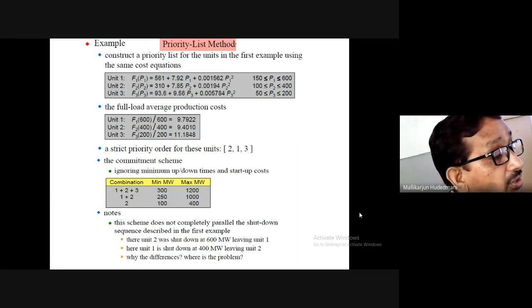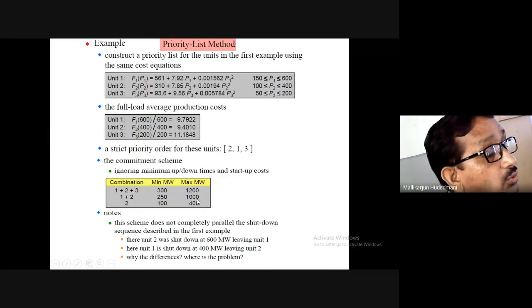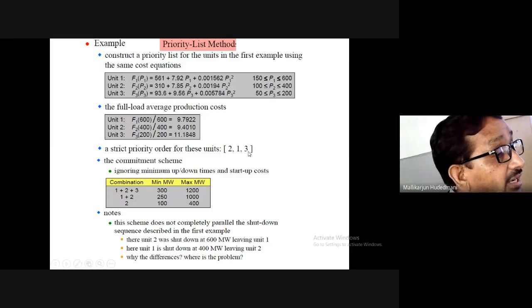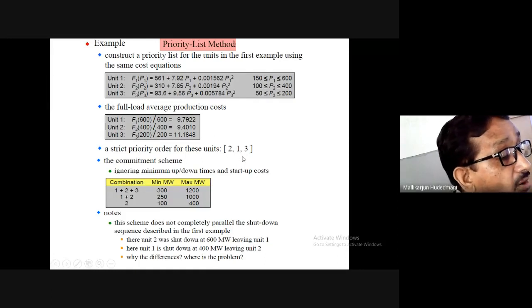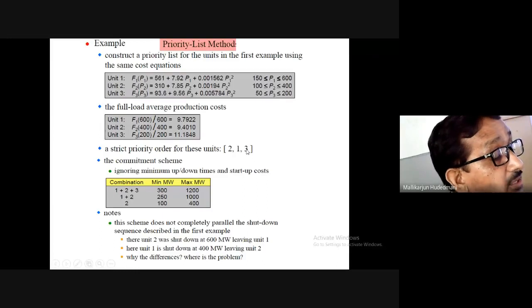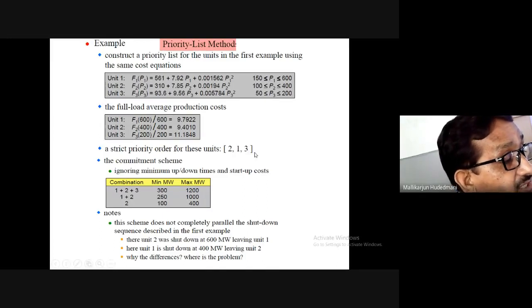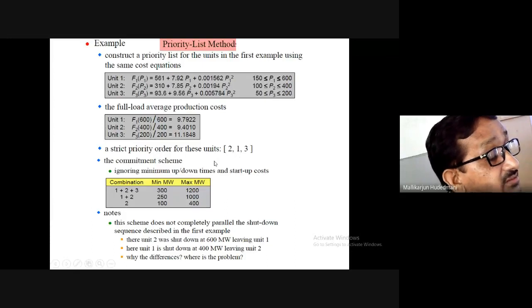Then look into this priority strict order, 2, 1, 3. If the load on the station is not 1200 and it decreases to 1000, I should remove the latest machine which is added. Third machine, remove this first, then 1, then 2. By the order itself, the first machine is the most fuel cost effective, the second is a little costlier, and the latest is costlier. Then the costliest one must be taken out first.